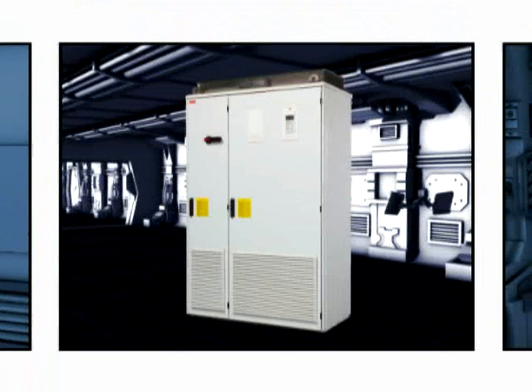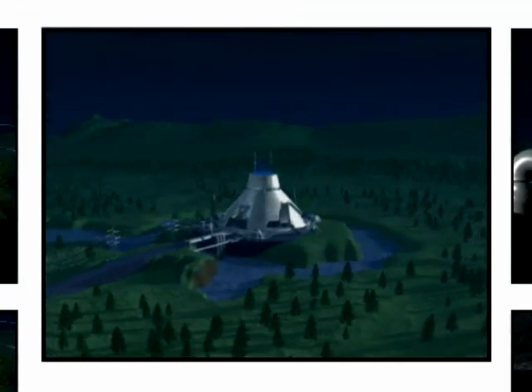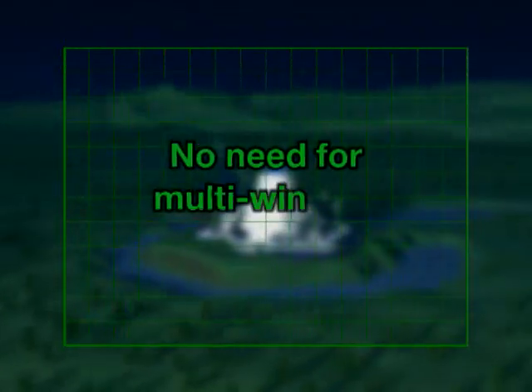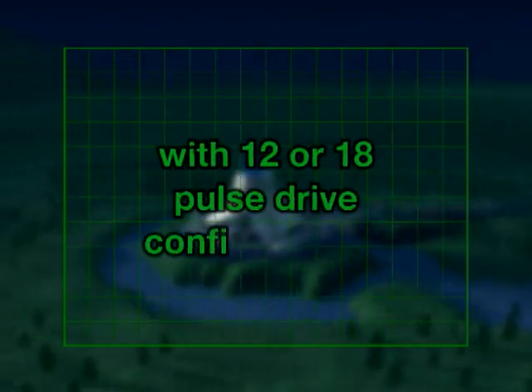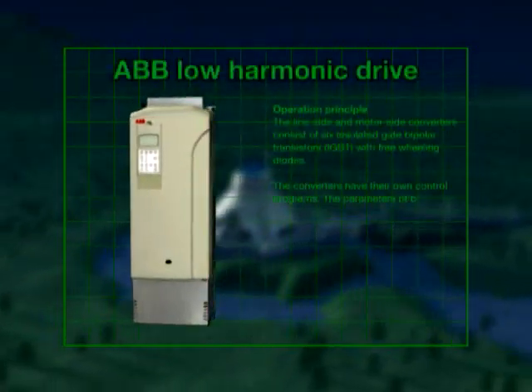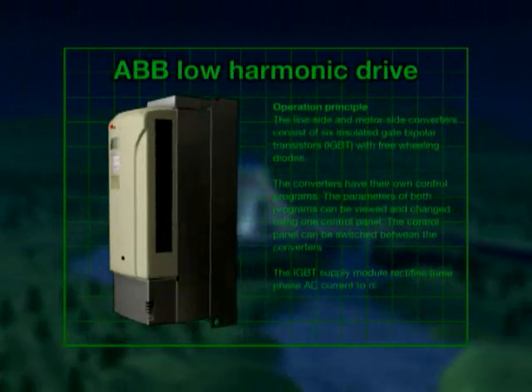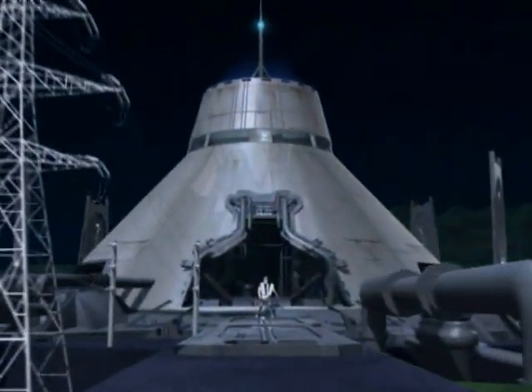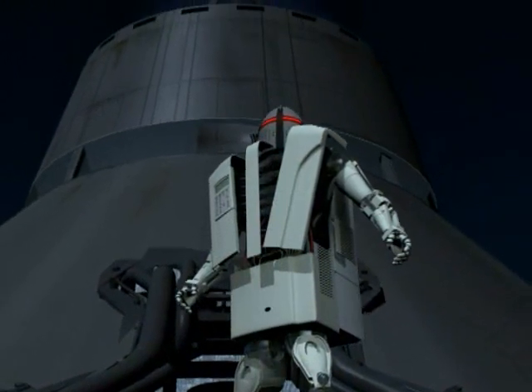Either wall or cabinet mounted, the Low Harmonic Drive rated from 5.5 to 2,800 kilowatts has no need for complex multi-winding transformers with 12 or 18 pulse drive configurations traditionally needed to control harmonics. In fact, harmonic performance with this ABB Low Harmonic Drive is better than with 12 and 18 pulse solutions, because it also handles line imbalance or other shortcomings in the supply network.